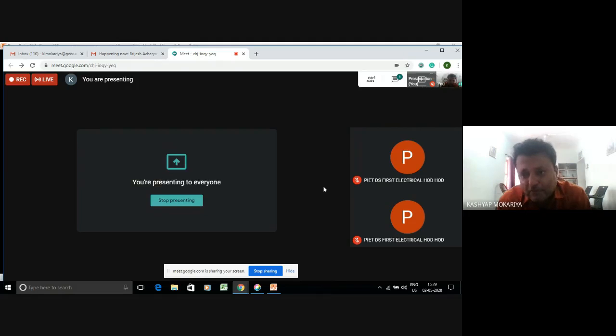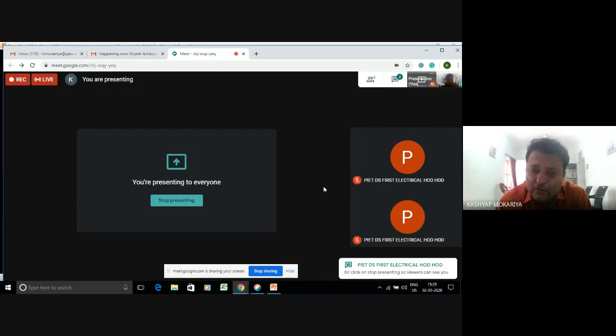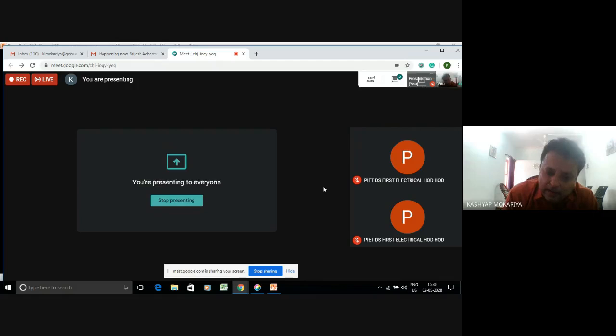Even if you have a simple resistive load, not only this type of circuit breaker, you even get the static breaker. Nowadays people use the static breaker also. In that case also, the resistive design is very simple, because you do not have any other issues like the student is asking. But regarding the breakers, I have explained. It works fantastically for all combined types of load: resistive, inductive, capacitive, all loads.